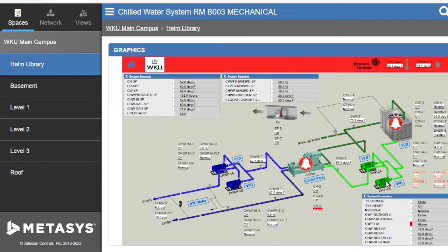Unfortunately, when this system was set up, the way that it was specified and everything within this system, there are no maintenance switches, there is no lead lag or anything like that within this system. Now what that runs into and what you can't see here is these two pumps here do have basket filters. Of course, being on the condenser side, it's always a good idea to have filters and things like that to keep trash out of your system.